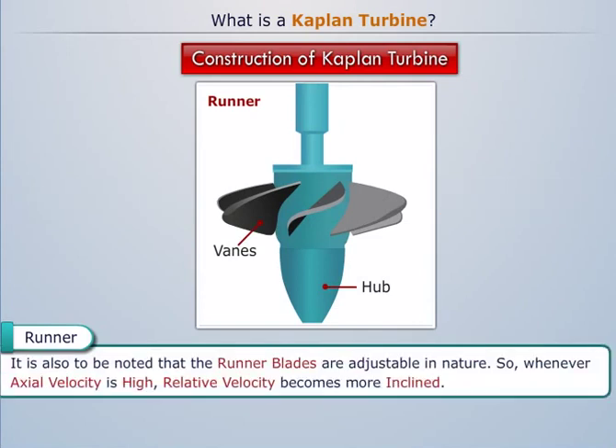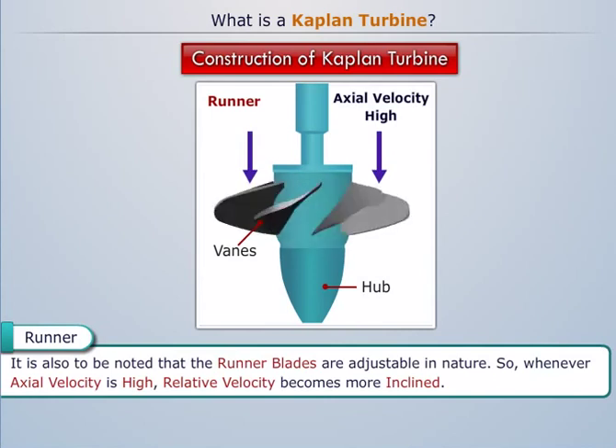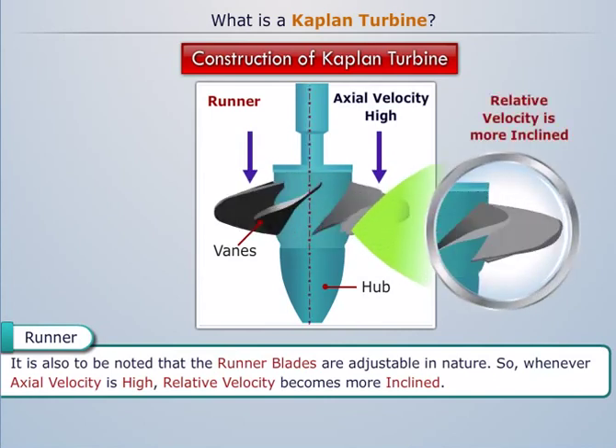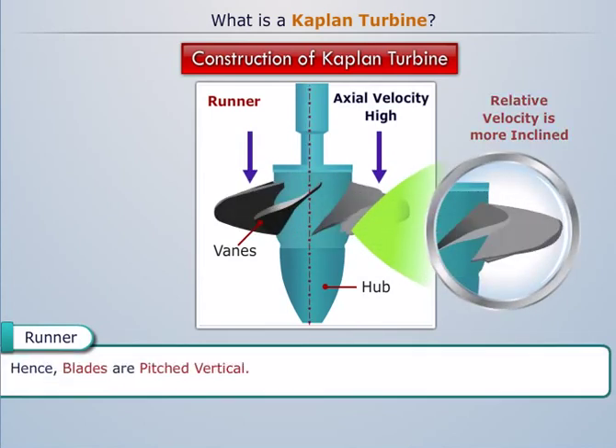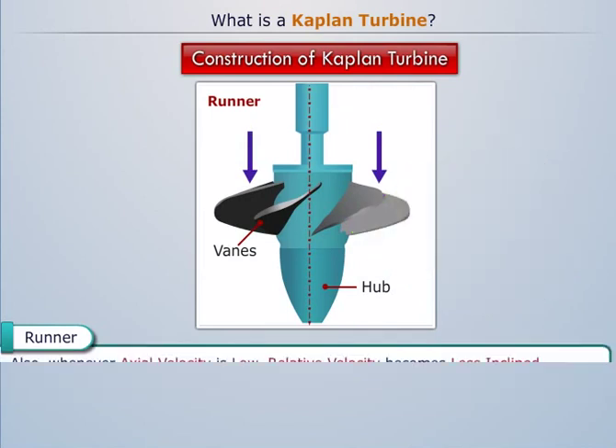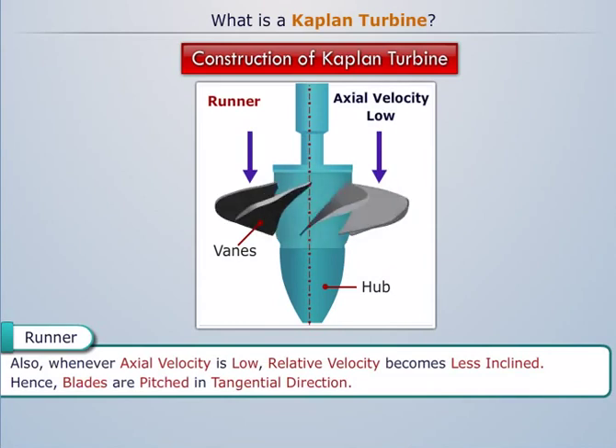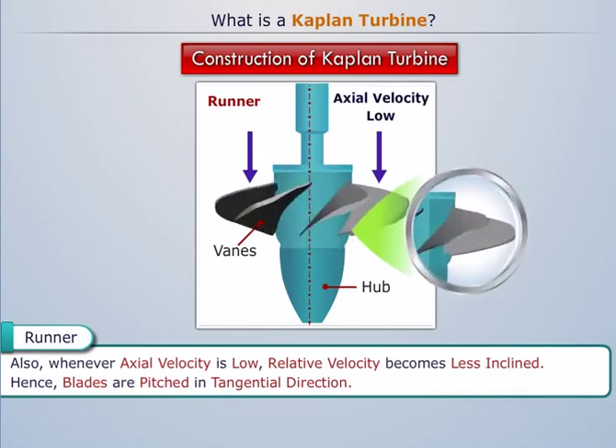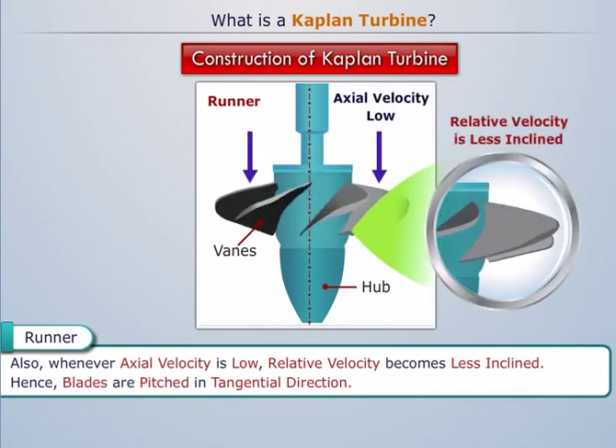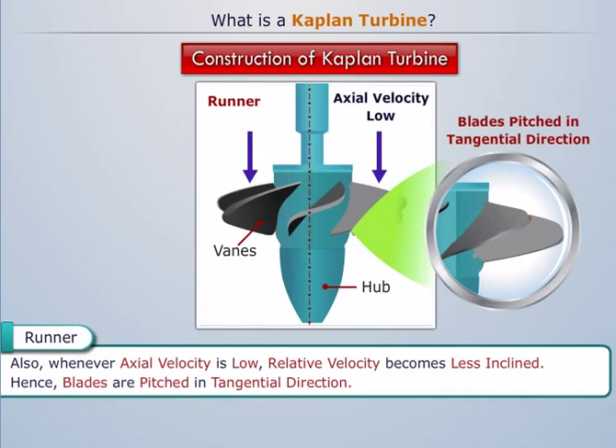It is also to be noted that the runner blades are adjustable in nature. So whenever axial velocity is high, the relative velocity becomes more inclined; hence, the blades are pitched vertical. Also, whenever axial velocity is low, the relative velocity becomes less inclined; hence, the blades are pitched in the tangential direction.